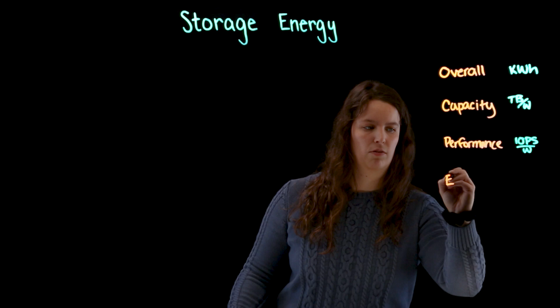The next thing is a little bit more of the big picture, which is really what is built around the actual storage device. This is the environment that is used as far as infrastructure to support the storage device from an energy perspective. There's 2 key metrics to consider here. The first is the operating temperature. Overall, at what temperature does your storage device need to be cooled down to perform to its metrics? If that's extremely low, then you're going to have a lot of overhead cooling energy consumption in your data center.